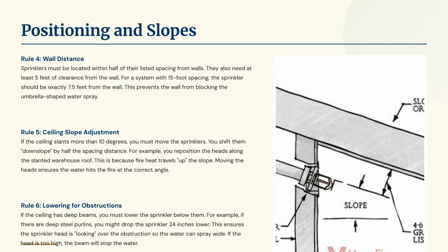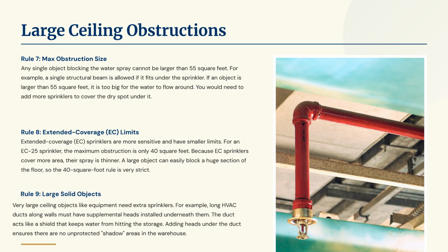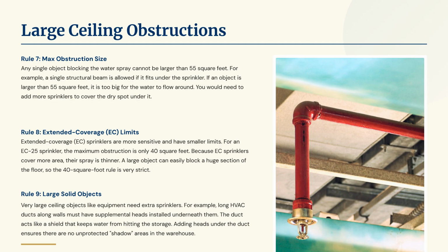Rule 4 states sprinklers must be within half their spacing from walls, with 5 feet of clearance. Rule 5 addresses ceiling slopes over 10 degrees, requiring a downslope shift. Rule 6 mandates lowering sprinklers below deep ceiling obstructions. Rule 7 limits obstructions to 55 square feet, while Rule 8 restricts them to 40 square feet for extended coverage sprinklers.